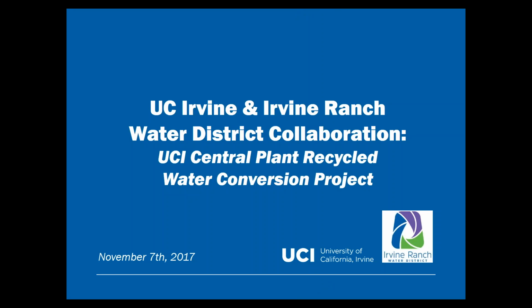Thank you. I'll be discussing a project under construction at UC Irvine that provides some examples of the water-energy relationship on a university campus. This is a collaborative project between UCI and Irvine Ranch Water District, our local water provider, to convert our central plant cooling towers from potable water use to recycled water use. The project relies on an innovative business model to achieve significant savings in both the embedded energy of UCI's water supply and also the amount of potable water consumed on the campus for energy production.